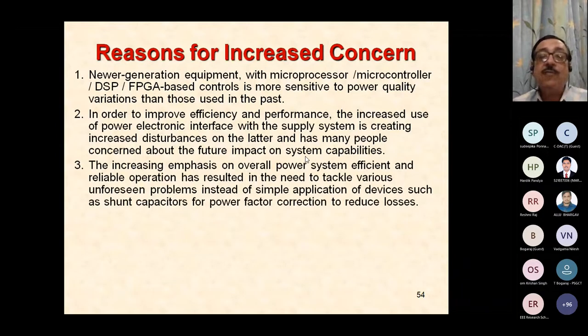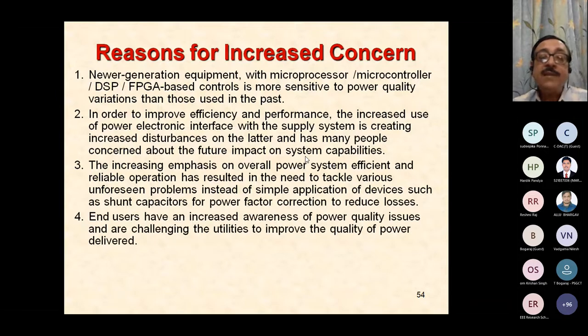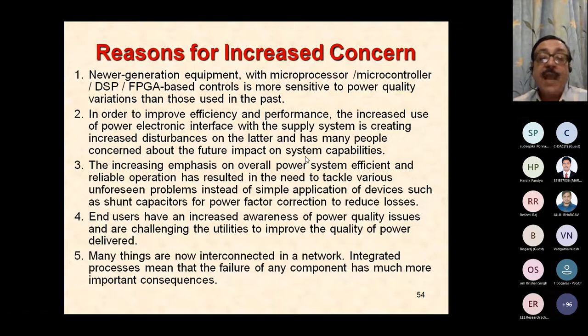The increasing emphasis on overall power system efficient and reliable operation has resulted in the need to tackle various unforeseen problems instead of simple applications like shunt capacitors or power factor correction. I'll show you today that power factor correction by a simple shunt capacitor connection is more risky at distribution level than what you would have thought 10 years back. End users have an increased awareness of power quality issues and are challenging the utilities to improve the quality of power delivered, and many things are now interconnected in a network. Integrated process means that the failure of any component has much more important consequences.